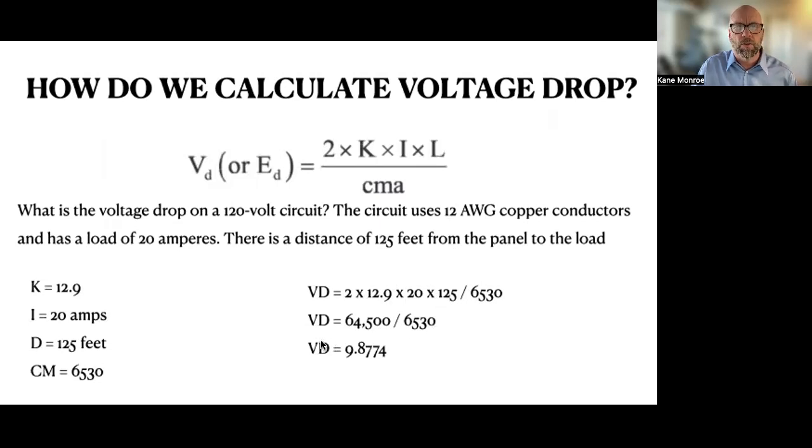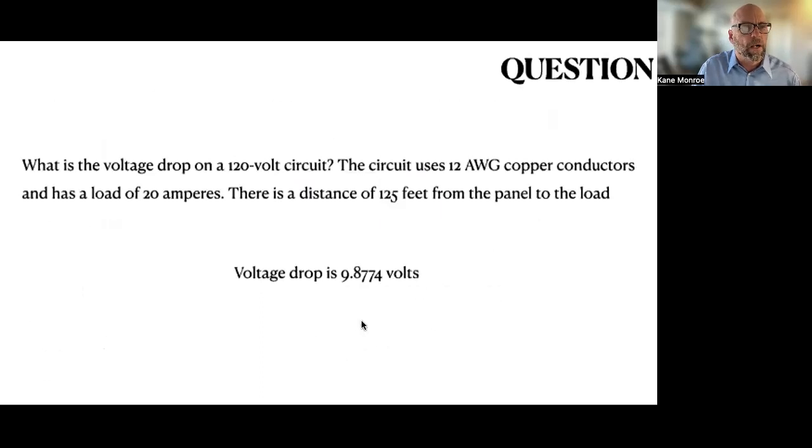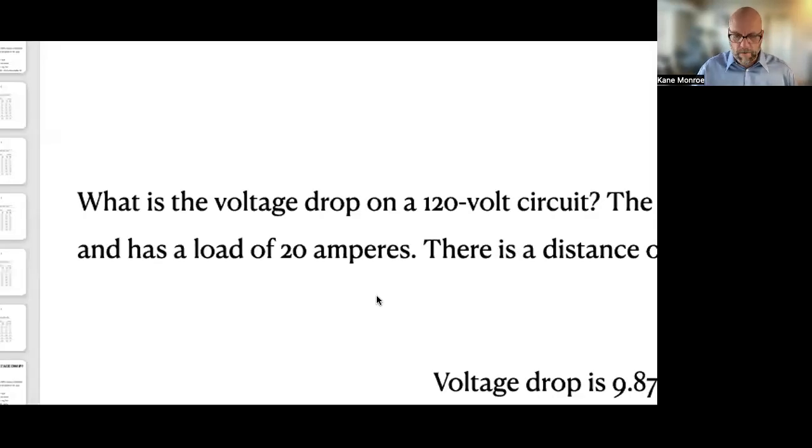And you get a voltage drop of 9.8774 volts. And so the answer, the question was, what's the voltage drop of 120 volt circuit? The circuit uses 12 AWG copper conductors and has a load of 20 amperes. And there's a distance of 125 feet from the panel to the load. The voltage drop is 9.874 volts.